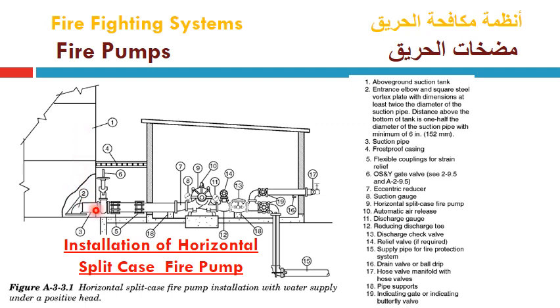discharged by the pump after it has been supplied from this water tank through the suction line, goes through the pump, then through the valving system attached here, and then goes to the building through this fire stand pipe. Pipe supports like number 18 may be added and located in different locations to affix the suction line on this wall and on this wall, and also here in the fire pump room, and the discharge line in the fire pump room. It should be affixed here and secured to prevent any damage which may happen when the pump suddenly starts, with these rigid concrete walls as commonly used in fire water tanks and fire pump rooms.